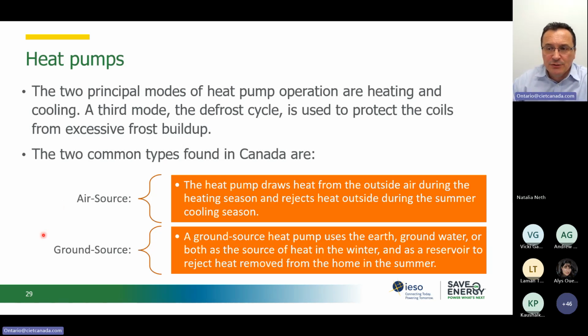But we also have an option to use ground source heat pumps. Multi-unit residential buildings may see this as an option because we are now using the ground. I mean, the cost to install the heat exchanger in the ground is higher, but we can more easily include one of these options when we look at centralized systems. So in the ground source heat pump, this is nothing new. I mean, we've seen installations based on ground source heat pumps since the 80s in Canada as a response to a push towards energy efficiency.